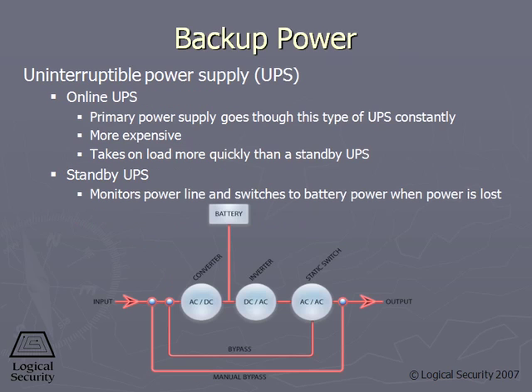Another alternative on a smaller scale are UPSs, or uninterruptible power supplies. There are two types. You should know them both. The first type is called the online UPS. In the online UPS, electricity flows through the battery into the devices, from power supply through the battery into the powered devices. In this case, if the power fails, the battery is already connected to the devices, and as a result, the switchover transition is instantaneous, and there generally is no spike associated with the transition from powered by the primary source to powered by the battery backup.